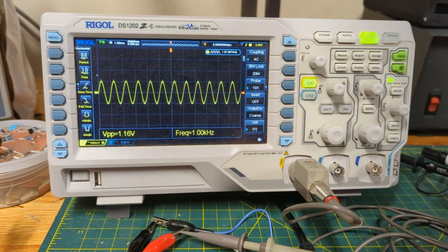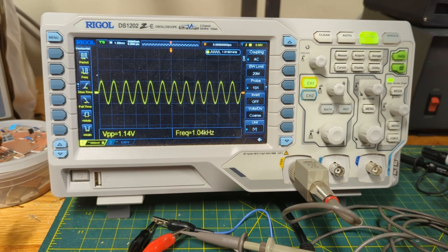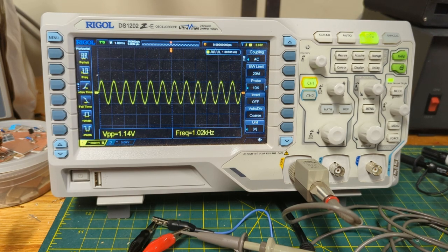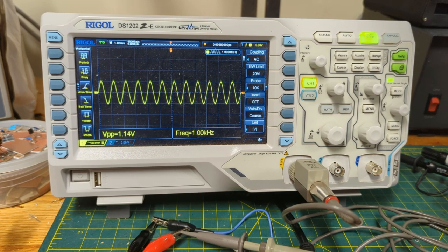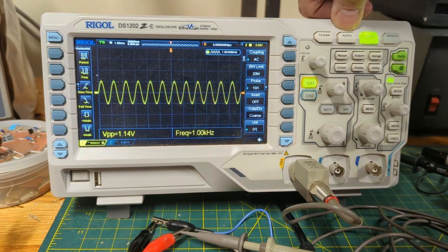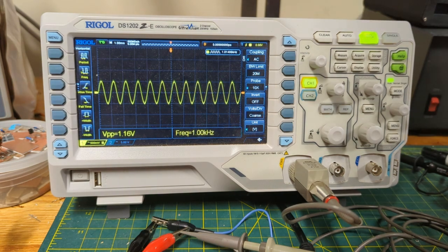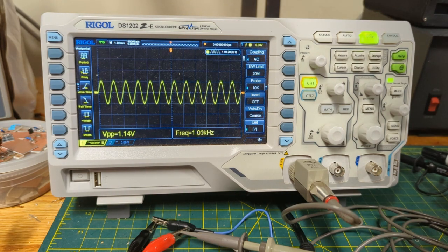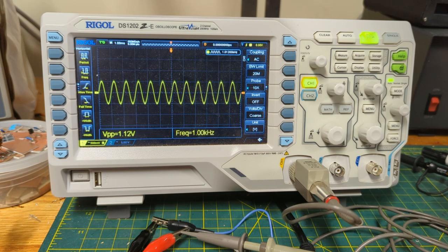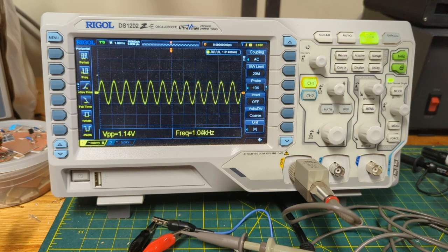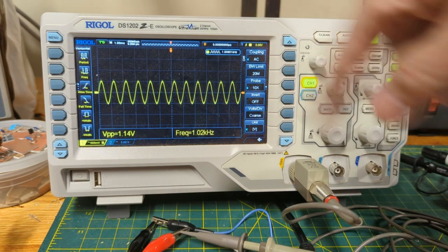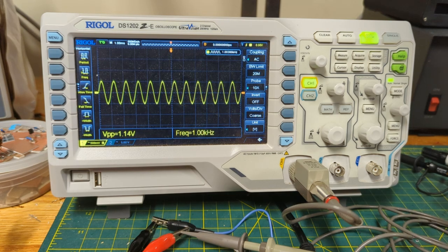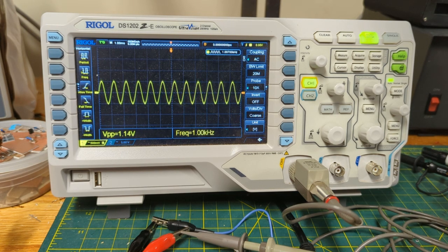I'm not going to cover triggering modes and all the other things. Just leave those on their automatic mode. A couple other things: Don't use the auto button on your scope. Learn to use the basic settings that I just showed you so that you can understand what you're seeing and why you're seeing it. The auto is a shortcut and it may change some of these settings in a way that you don't want. For instance, it'll probably turn on DC coupling, which we don't want.